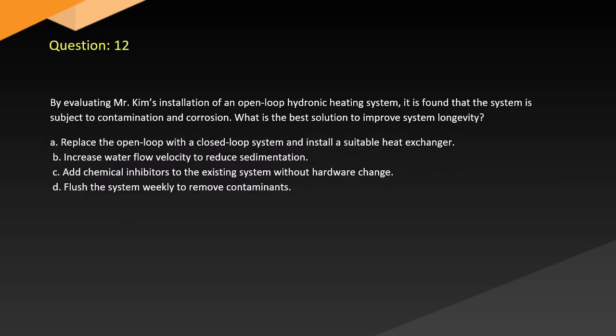Question 12. By evaluating Mr. Kim's installation of an open-loop hydronic heating system, it is found that the system is subject to contamination and corrosion. What is the best solution to improve system longevity? A. Replace the open loop with a closed-loop system and install a suitable heat exchanger. B. Increase water flow velocity to reduce sedimentation. C. Add chemical inhibitors to the existing system without hardware change. D. Flush the system weekly to remove contaminants.